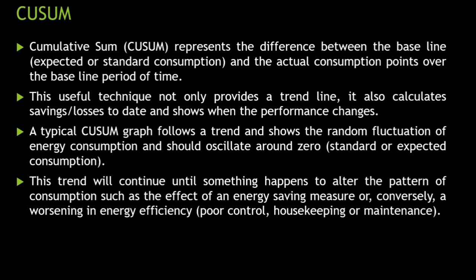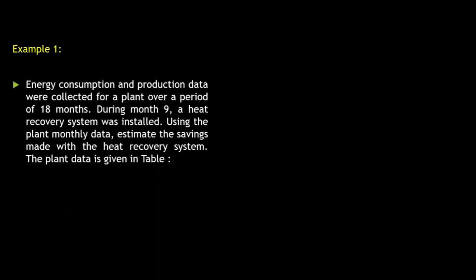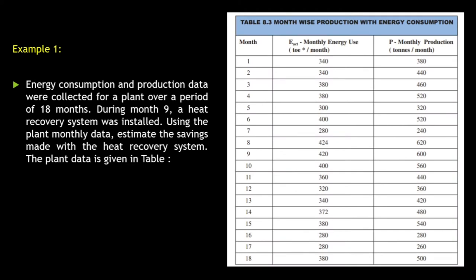This trend will continue until something happens to alter the pattern of consumption, such as the effect of an energy saving measure, or conversely a worsening in energy efficiency — that is, if there is poor control, poor housekeeping or maintenance, then the fluctuations will be too much. To start with, I have this example where energy consumption and production data has been given for 18 months. During the 9th month, a heat recovery system was installed. Using the plant monthly data, we will estimate the savings made with the heat recovery system.